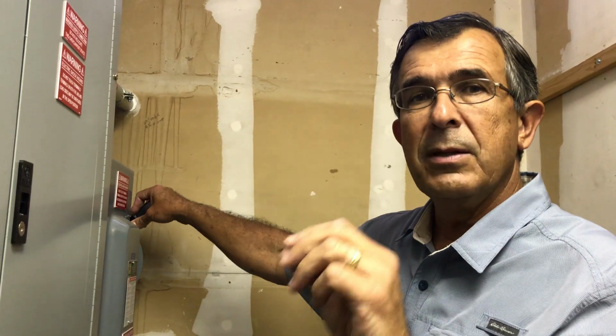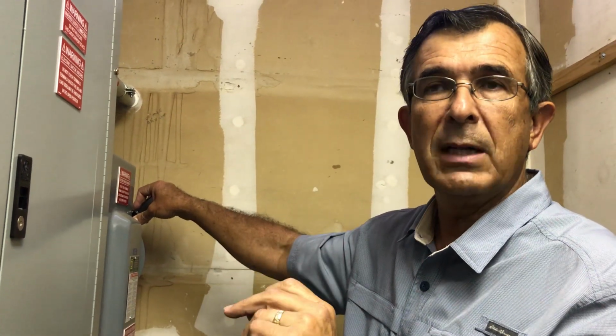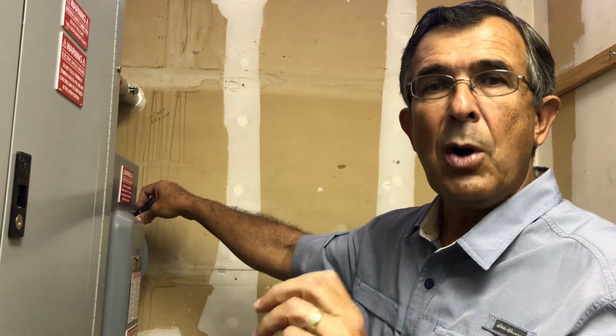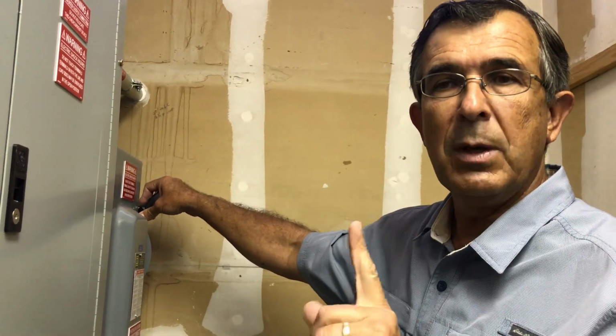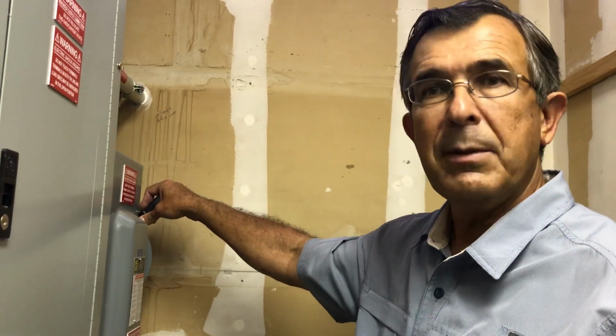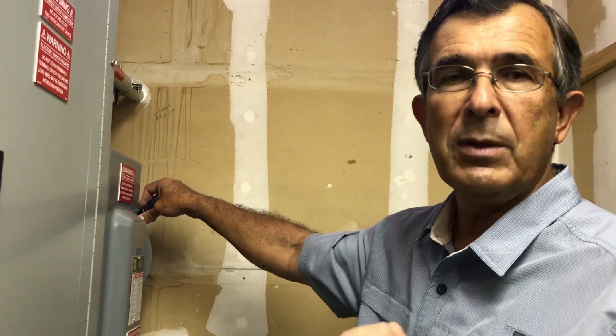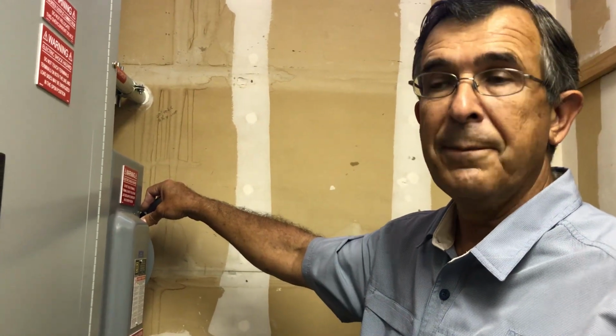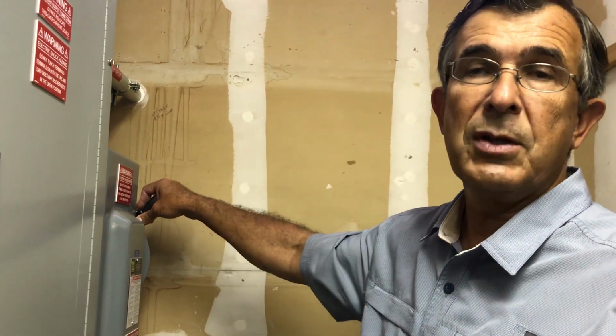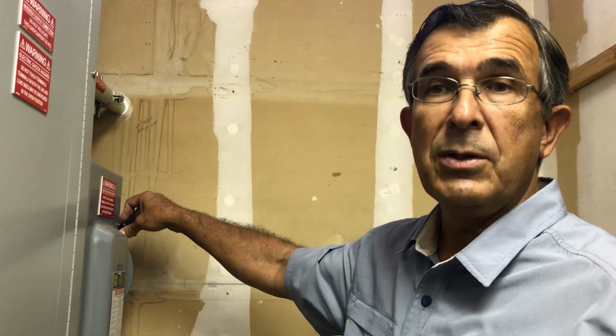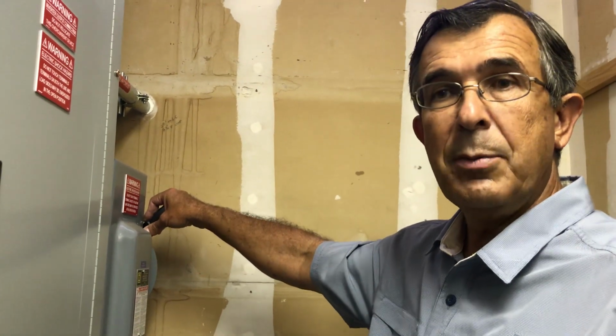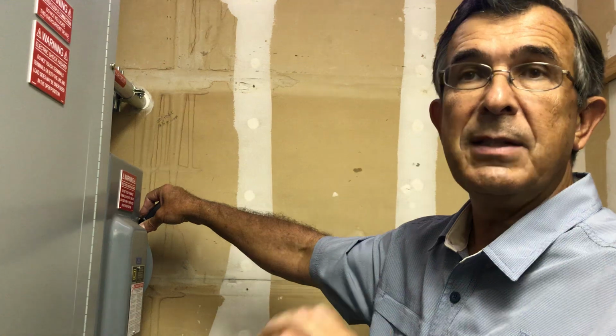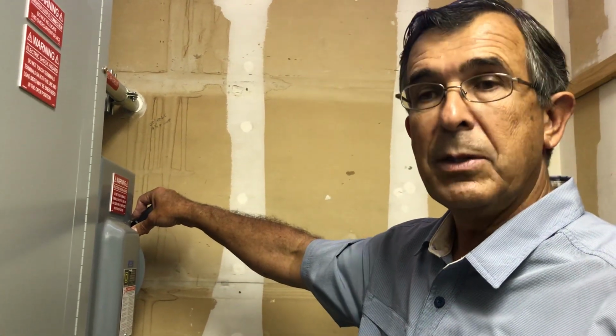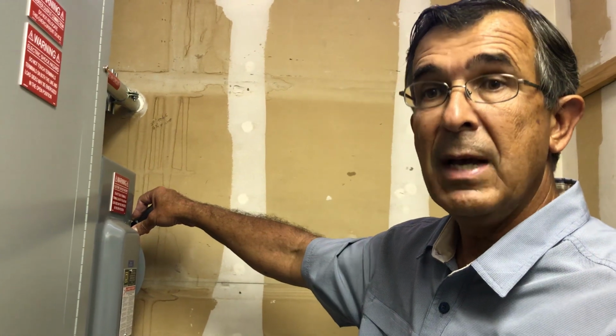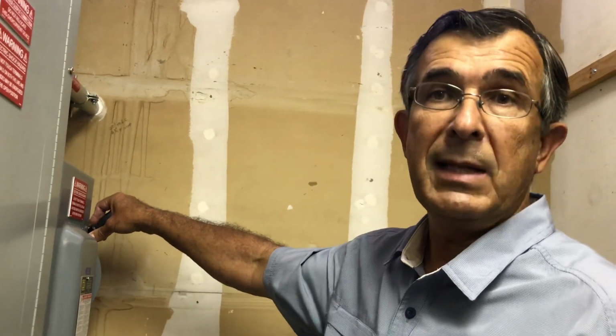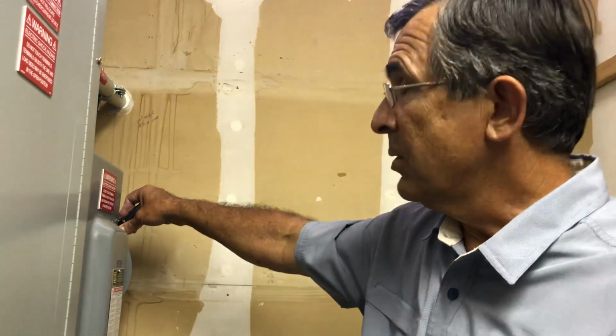So the second that happens, the SolarEdge power optimizers, the brains that we talked about earlier out there at the solar modules, turn the output from the solar modules to just 1 volt. So if you've got, let's say, 20 optimizers connected on a string, you'll have 20 volts maximum. So the system becomes very safe. When the system's on, many of those same circuits are producing nearly 1,000 volts. So you can imagine those solar modules continue to produce electricity even when the whole system's off, and it just sits out there at as much as 1,000 volts, which can make the system very dangerous to service if you don't know what you're doing. But with the SolarEdge technology, bringing it down to 1 volt per module really makes it safe.